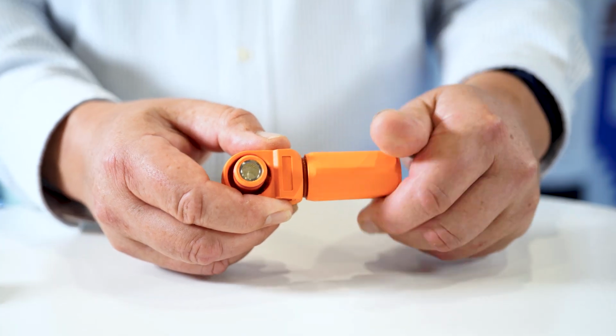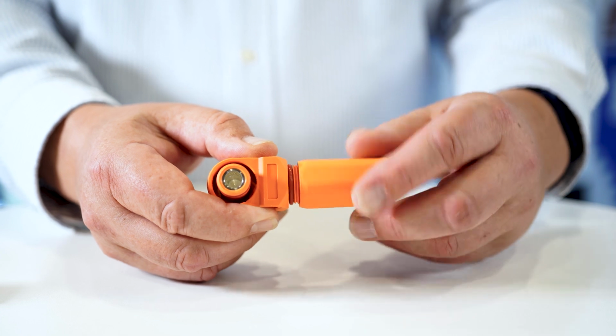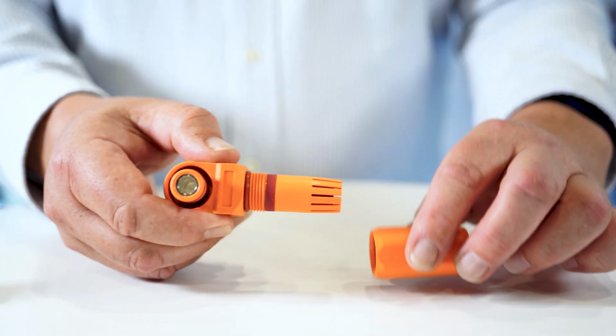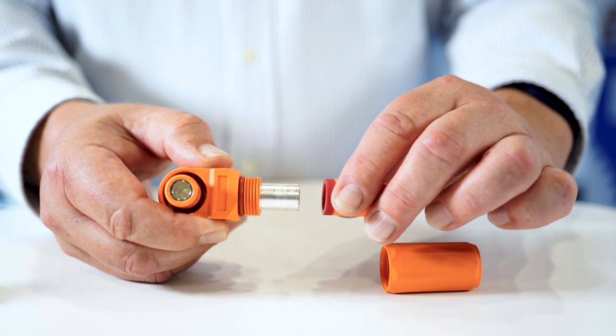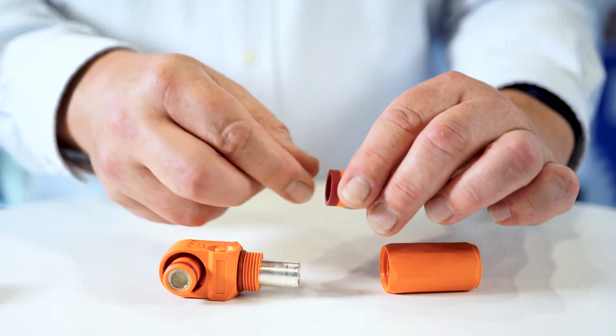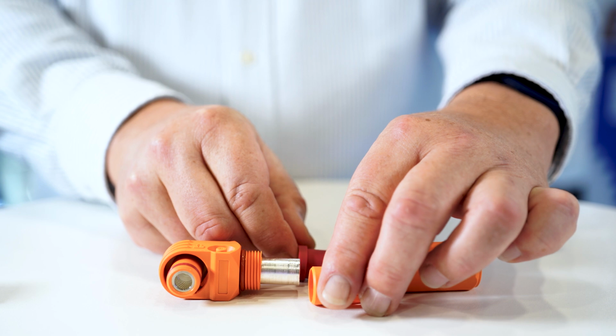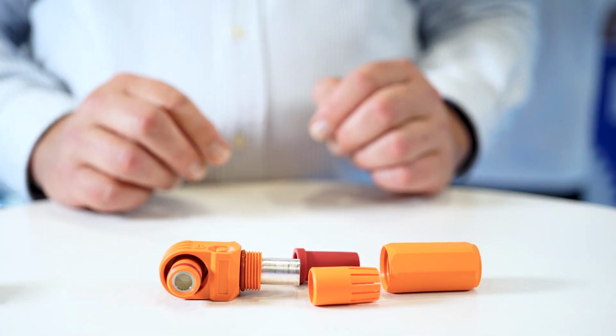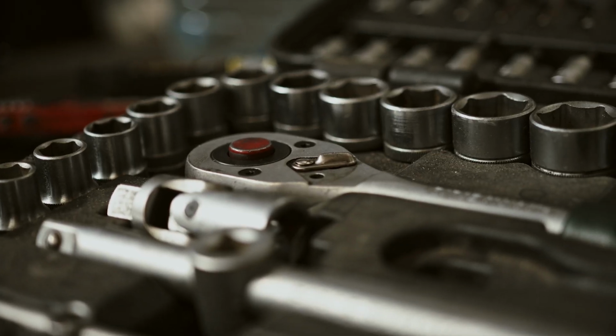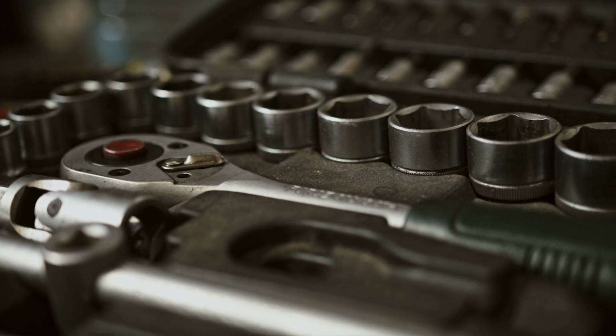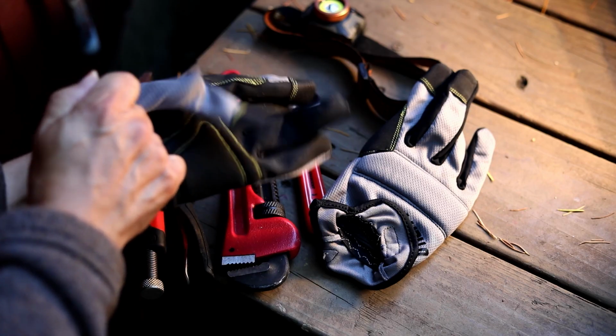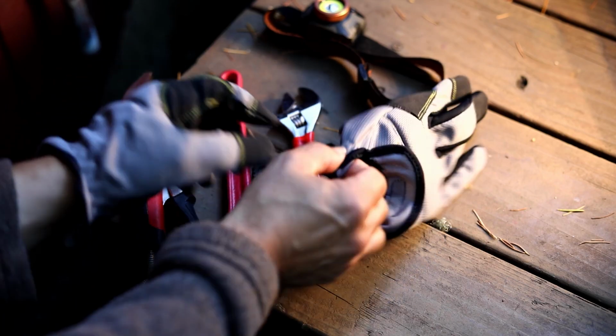These connectors are very often terminated in the field, so they need to be terminated without special tooling, and have a variety of different termination options. The AdamTech ES series has the standard crimp terminal, but also busbar terminals, threaded hole terminal and through hole connection options, all of which use standard field tools that a typical installation engineer would carry with them in their toolbox or vehicle.